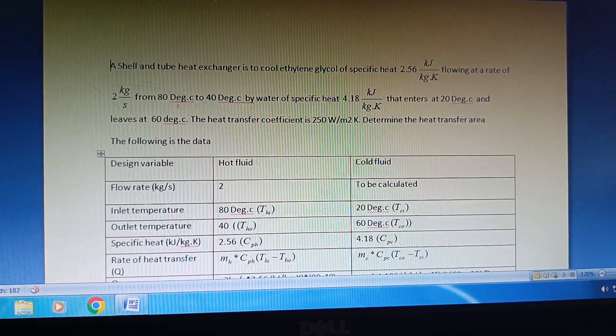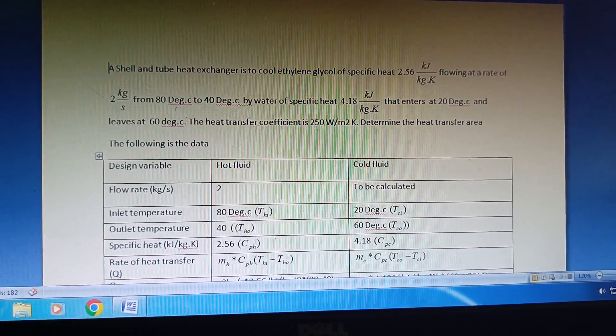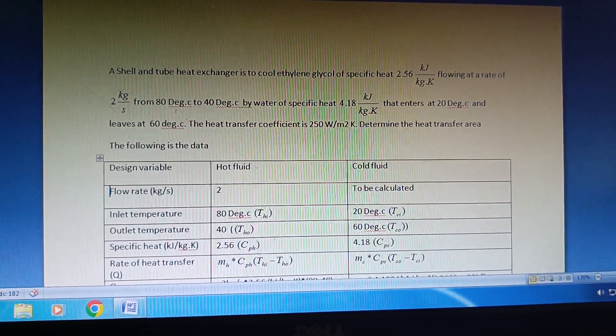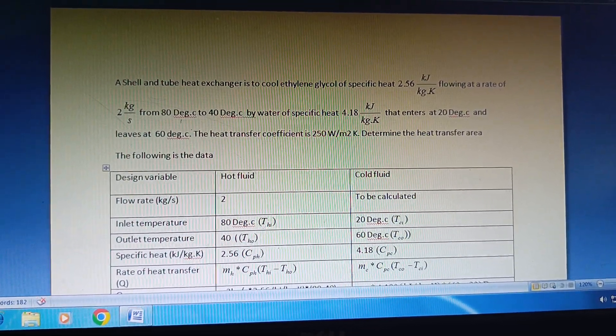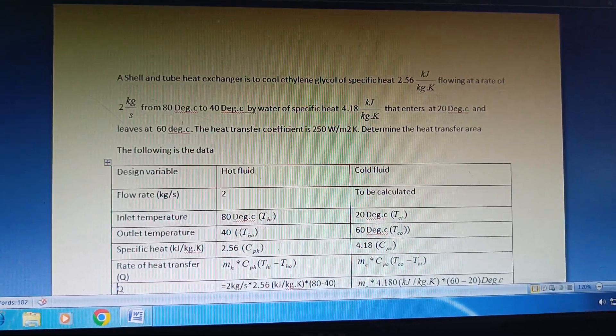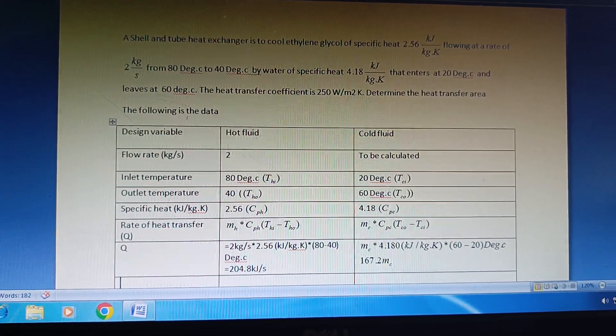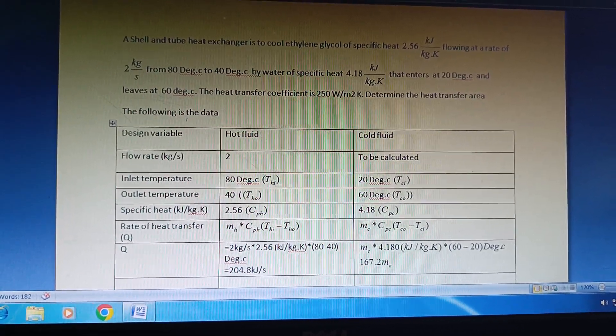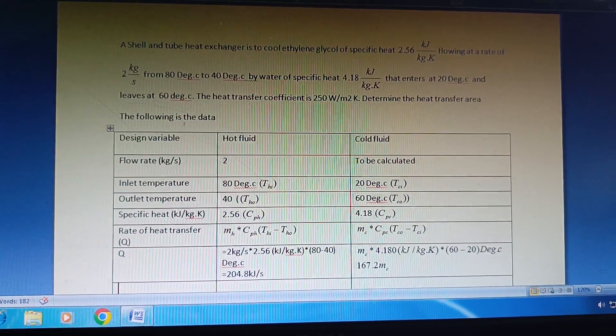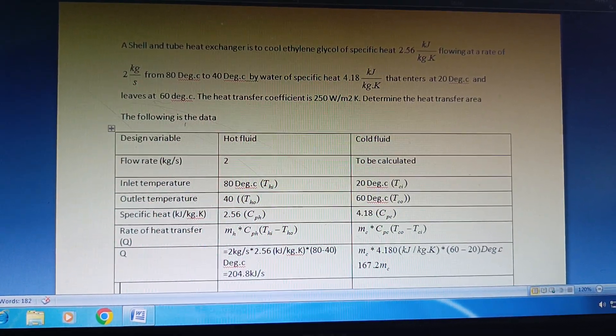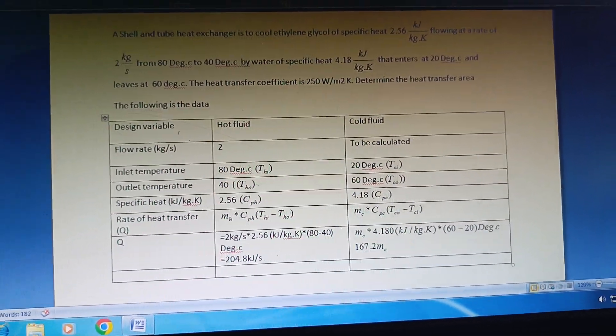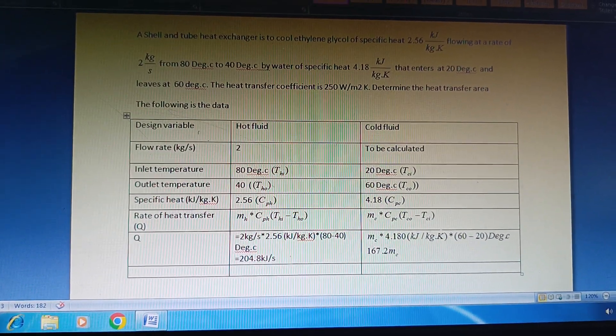To calculate the heat transfer area, we first need the rate of heat transfer. The hot fluid parameters — specific heat, mass flow rate, and temperature difference — are given. The rate of heat transfer is purely sensible heat transfer, given by: Q = ṁ_hot × Cp × ΔT = 2 × 2.56 × (80 − 40) = 204.8 kJ/s.